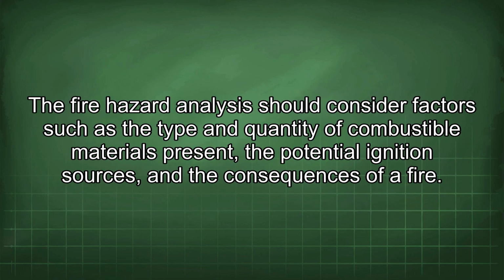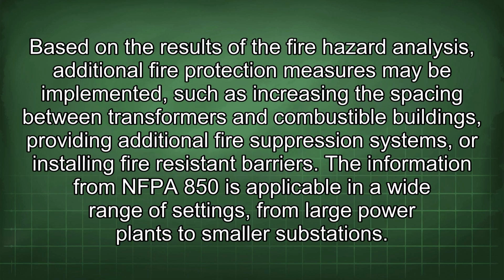The fire hazard analysis should consider factors such as the type and quantity of combustible materials present, the potential ignition sources, and the consequences of a fire. Based on the results of the fire hazard analysis, additional fire protection measures may be implemented, such as increasing the spacing between transformers and combustible buildings, providing additional fire suppression systems, or installing fire-resistant barriers. The information from NFPA 850 is applicable in a wide range of settings, from large power plants to smaller substations.